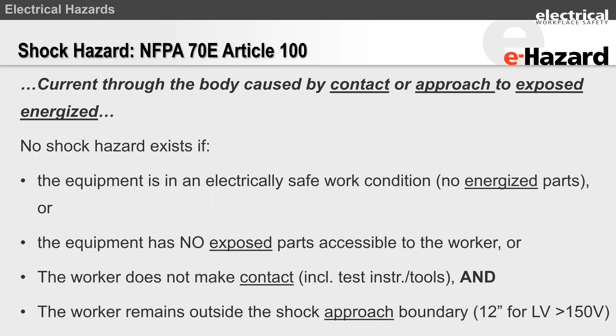Then you have another hazard called the arc flash hazard. Those are the only two hazards we need to be concerned about around electricity: shock and arc flash. Arc flash occurs when a piece of equipment fails and releases energy. So the question is, exactly when are we exposed to this hazard, or when is this hazard present? What NFPA 70E states is that the likelihood of an arc flash incident increases with exposed energized conductors and circuit parts, which basically means when you have a shock hazard, you will have an arc flash hazard.